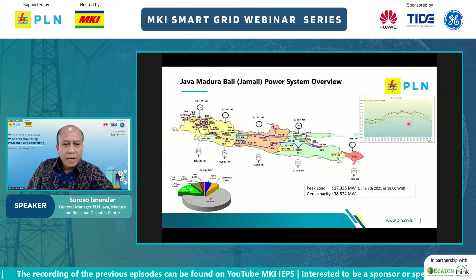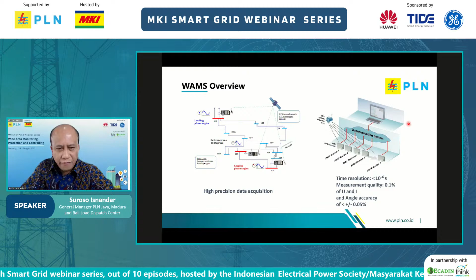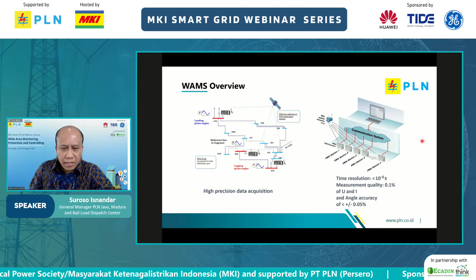Looking at the wide area monitoring system overview, to put it simply, it relies on the application of synchrophasors or phasor monitoring units, which give us more sampling time. Within one cycle we take a sample, so using 50 Hz, we are talking about 50 samplings per second, with PMUs scattered all over the place.